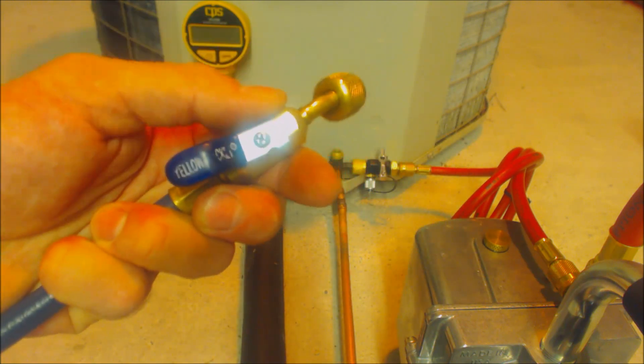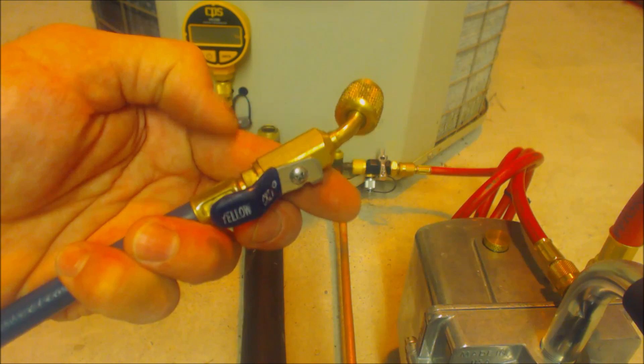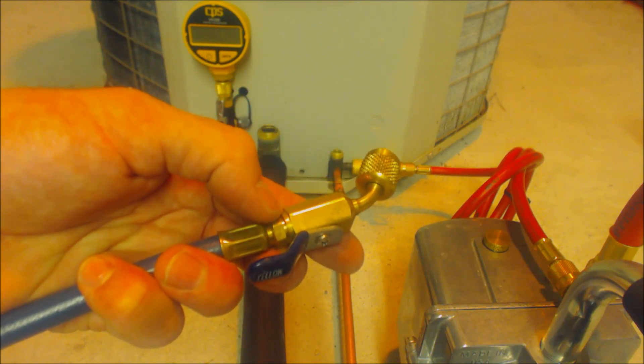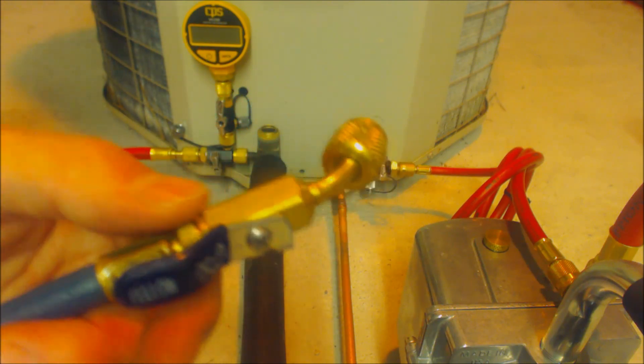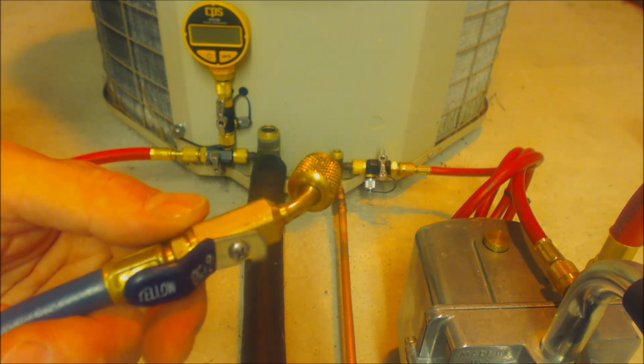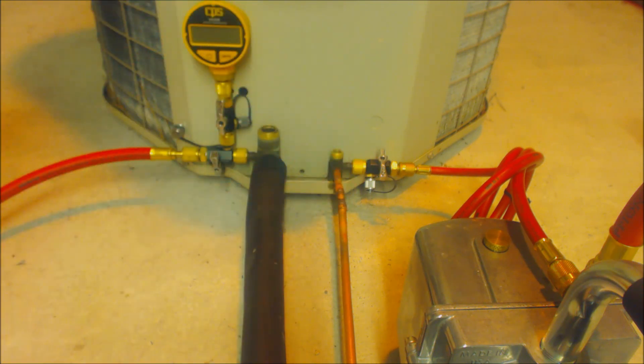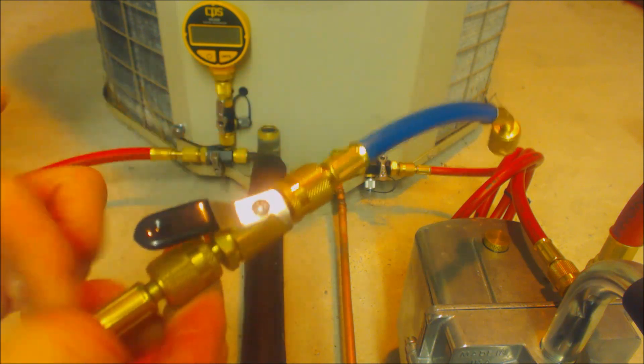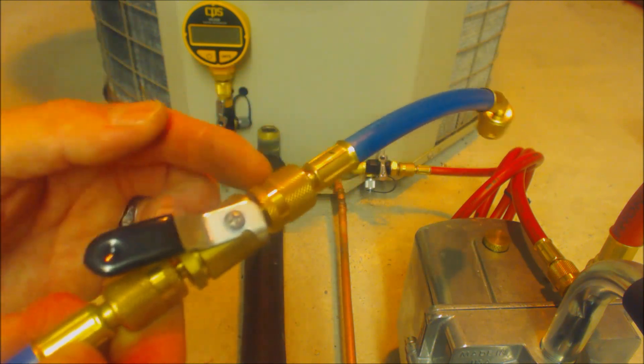Another thing could be that this valve right here is potentially leaking or this connection could be leaking. A lot of times this stuff will hold during the pressure test, but then when you're vacuum pumping, that's when you end up having a problem. It could be that you have just too many connections and maybe something in here is leaking.